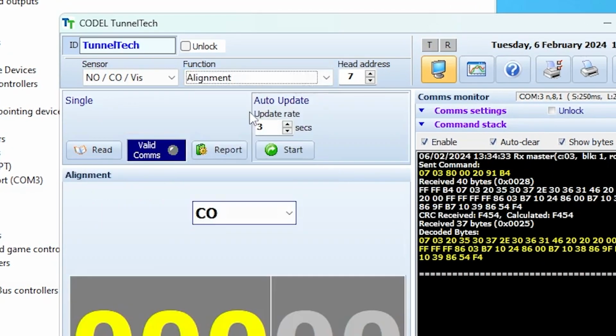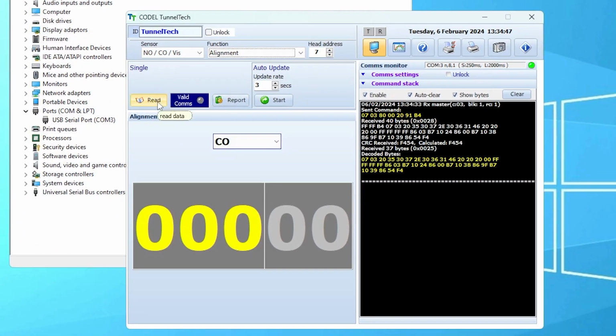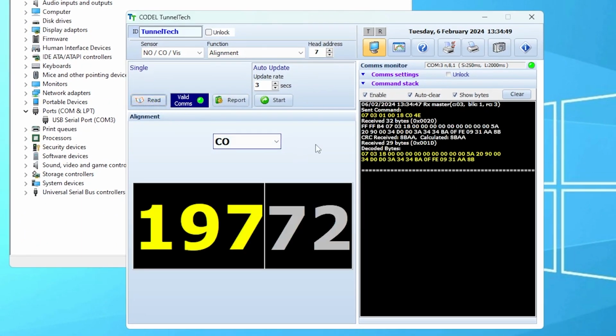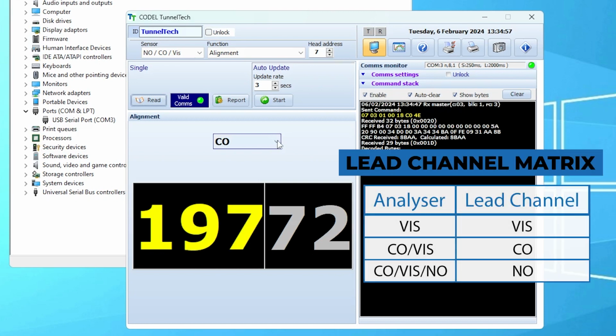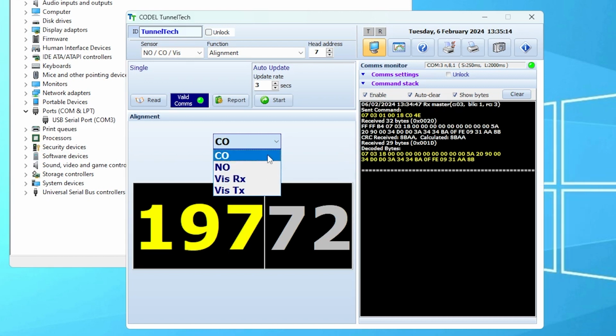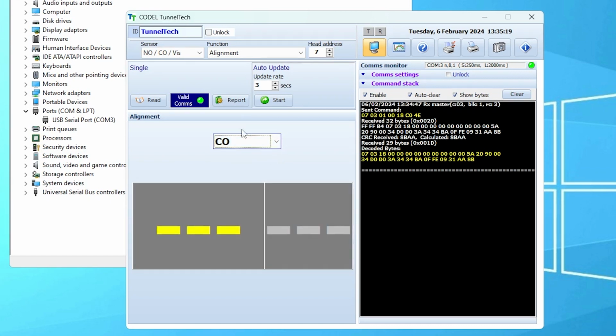Clicking read on this page will update the number, which we're going to use to align to. You must take care when selecting which instance to align to. In the case of a system that has an NO measurement, you always align to the NO channel. If there's no NO measurement, like a CO Viz monitor, you'd select the CO channel. If it's a Viz only, you select the Viz RX. In our instance, this system is a CO only monitor, so we're going to use the CO detector level to align to.